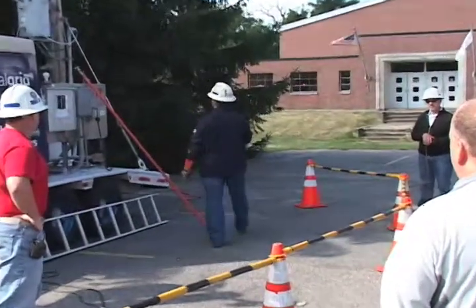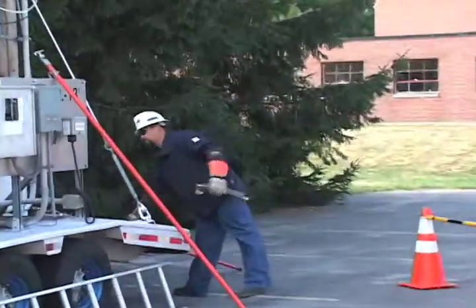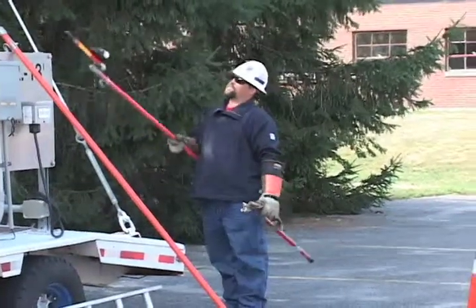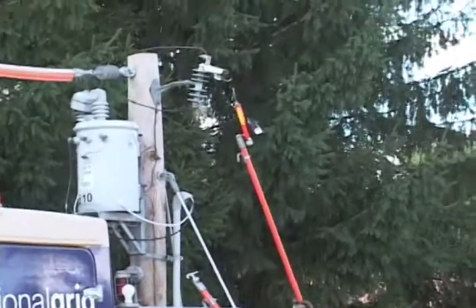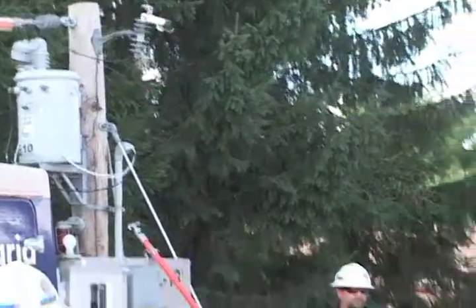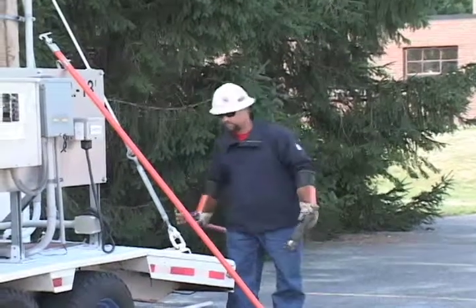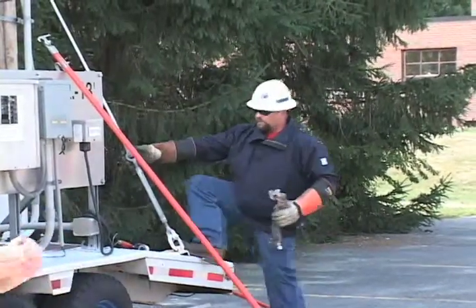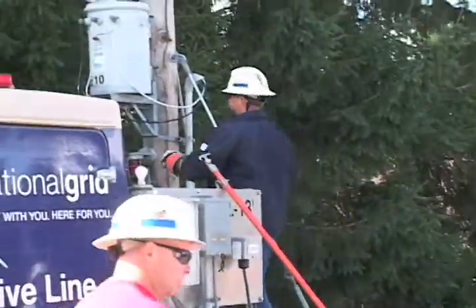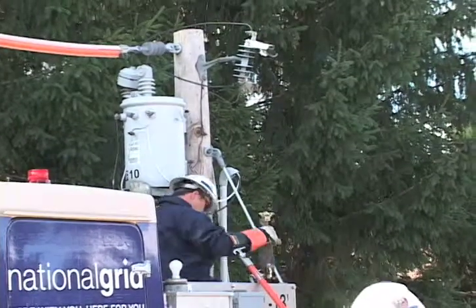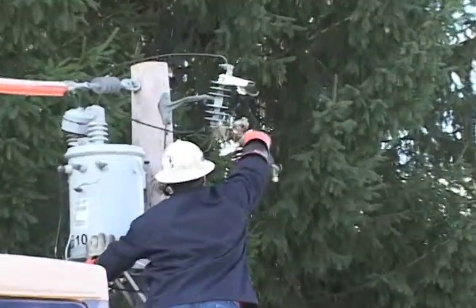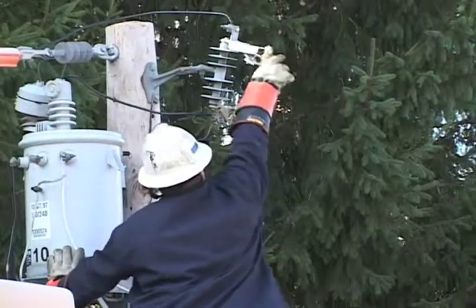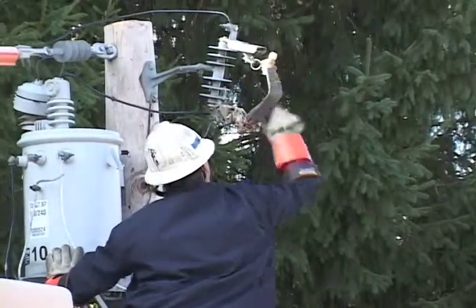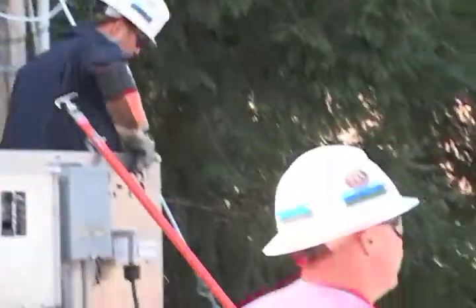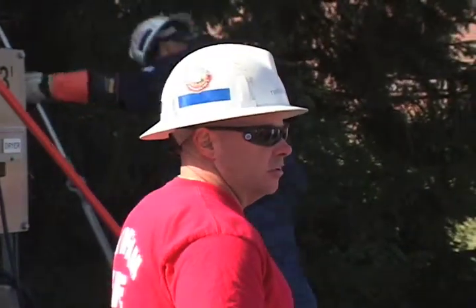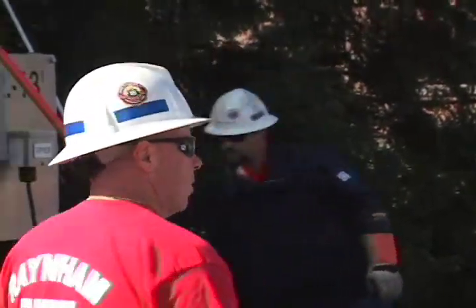I'll show you when I put this up there, we have a high voltage tester. I can show that the voltage will be at the top, and the voltage will go right through the fire hose to the bottom. Like I said earlier in Joe's presentation, we don't consider anything dead until we actually physically test it with a high voltage tester and then ground it. At that point we'll consider it dead, but up until then we consider every conductor energized until proven not and grounded.